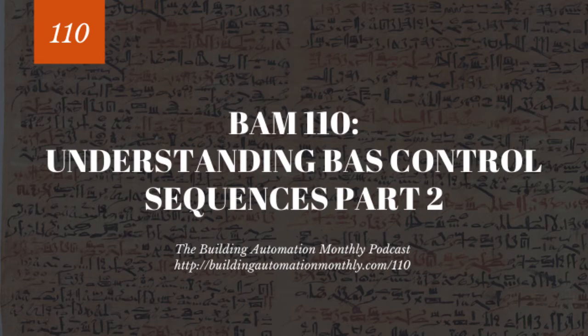Oftentimes folks will think that minimum airflow means the amount of outdoor air that you need for that space. So let me give you an example. If you needed 5 CFM of outdoor air per person and you had 10 people in a space, you'd say, okay, then I need 50 CFM of outdoor air.